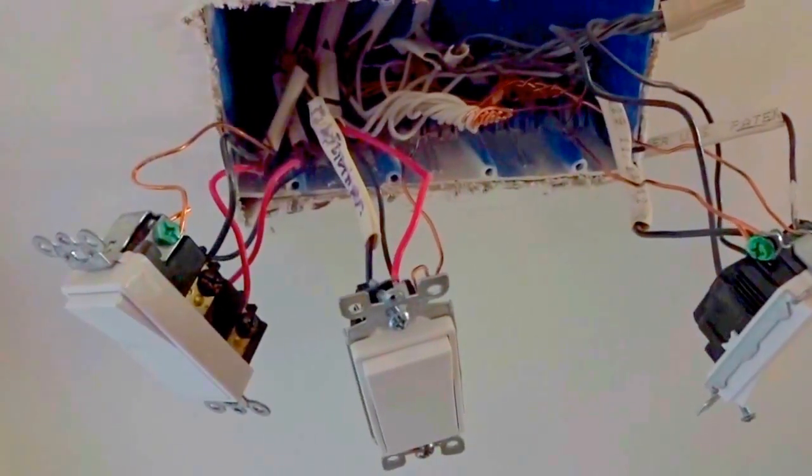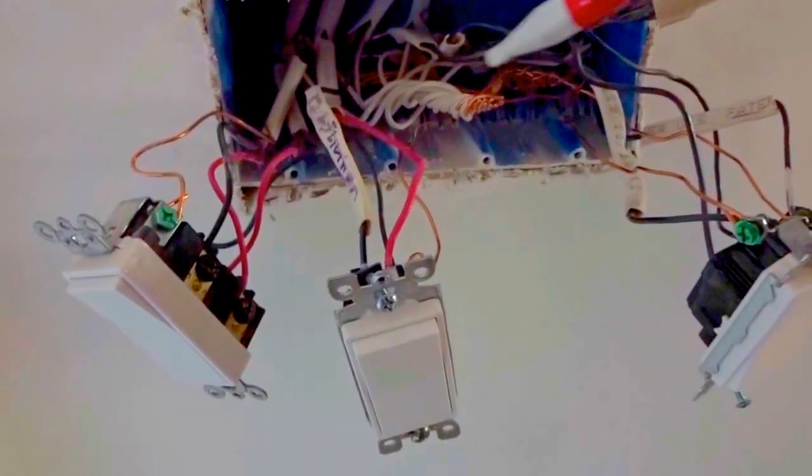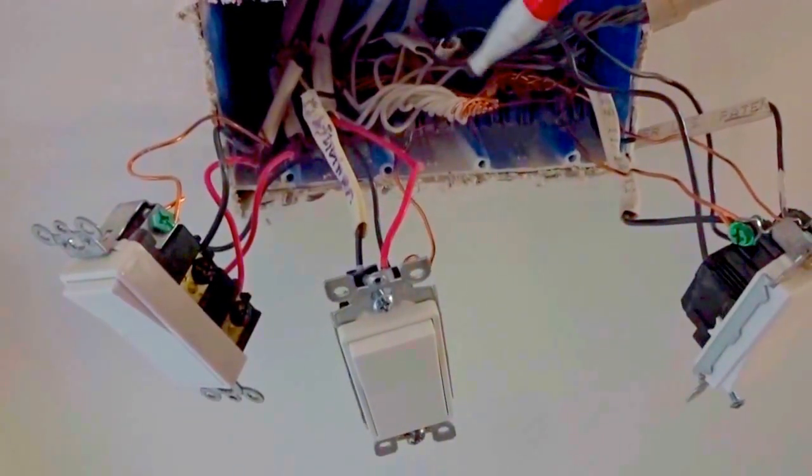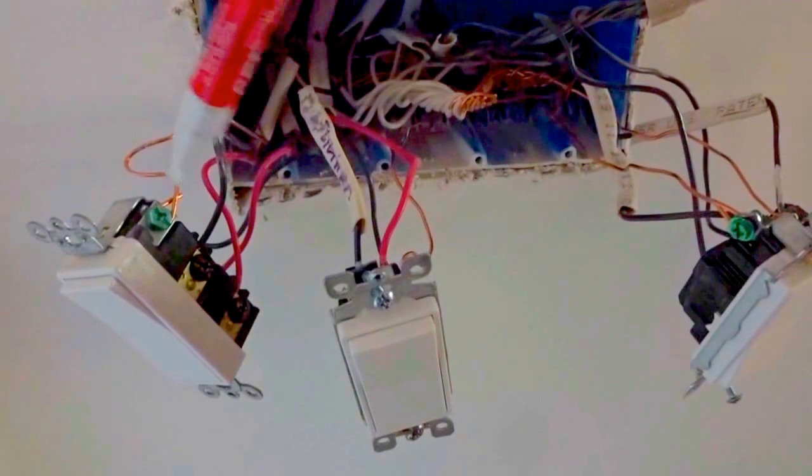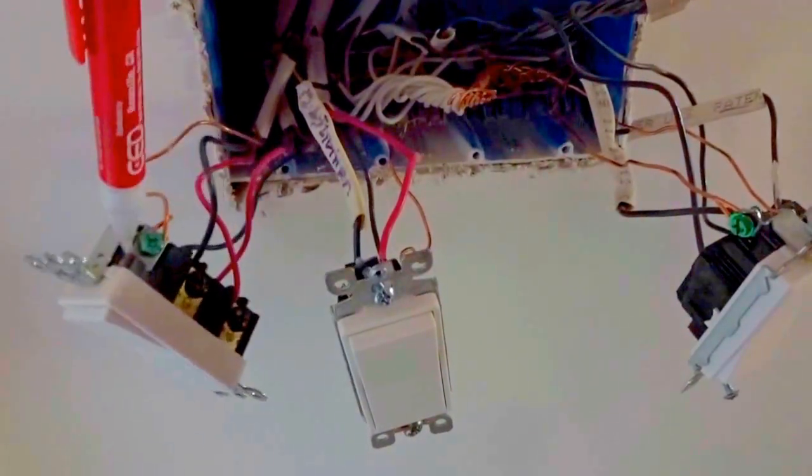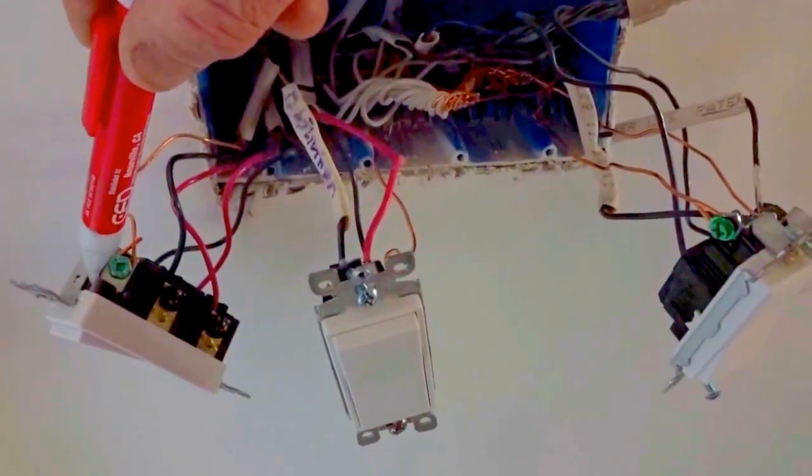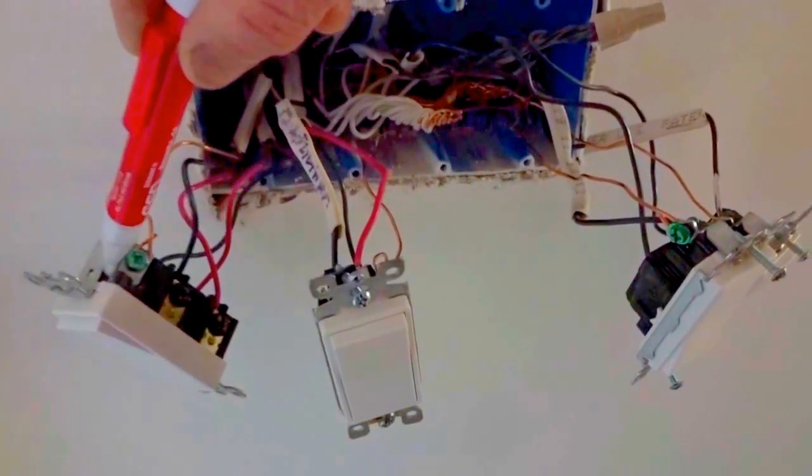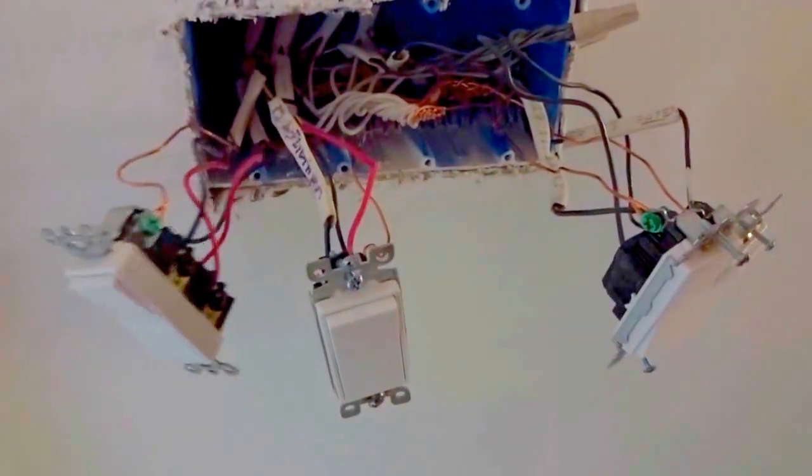I'm just going to separate these neutrals out appropriately so that the two sets of travelers feeding this, coming in and out of this four-way switch, will have the neutrals tied together isolated from the rest of them.